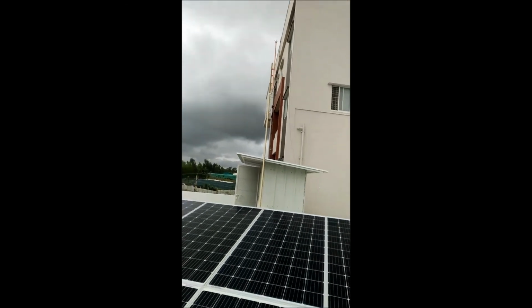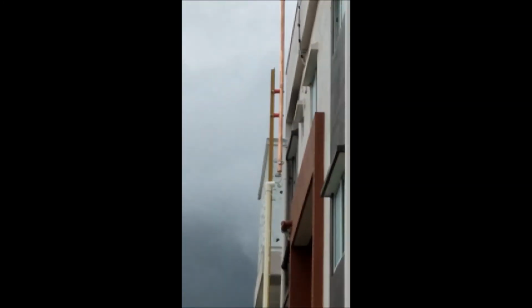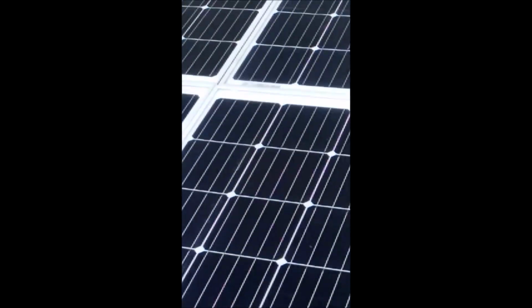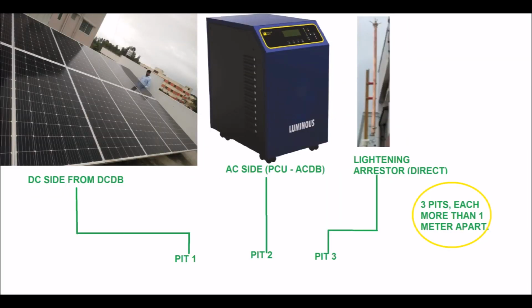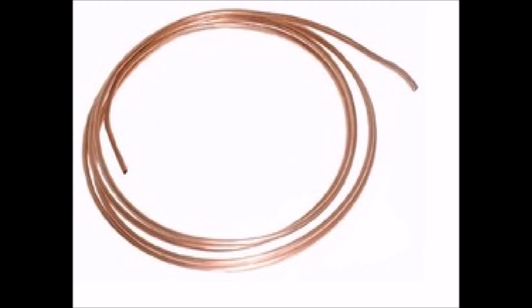Lightning arrestor is fixed at 3 meter height above the panel. Earthing is an important part of the installation. We have taken 3 earths, one for panel, one for the AC inverter side and one for the lightning arrestor.